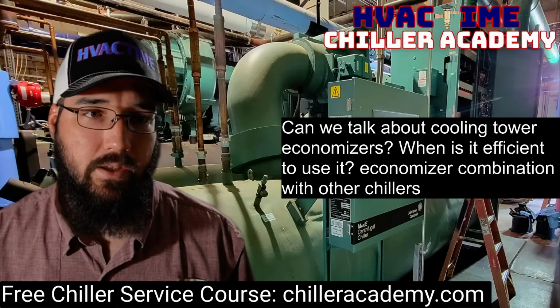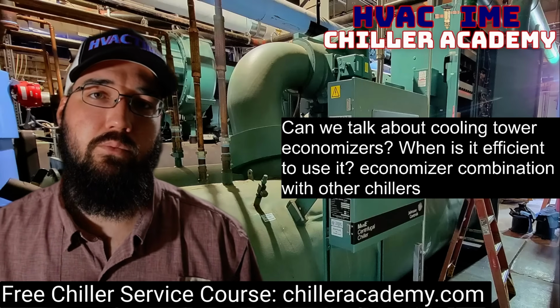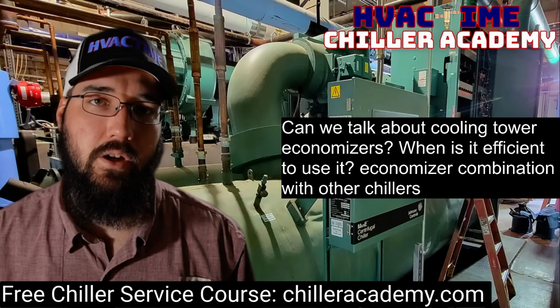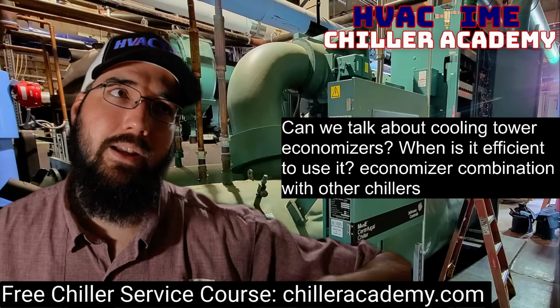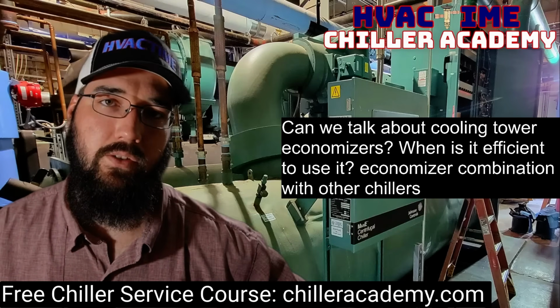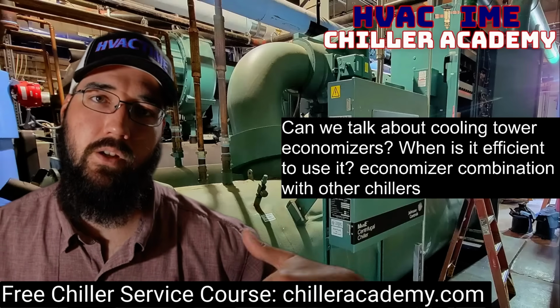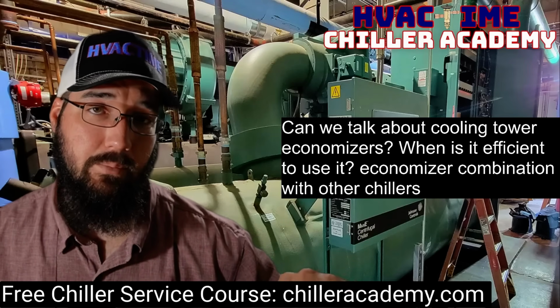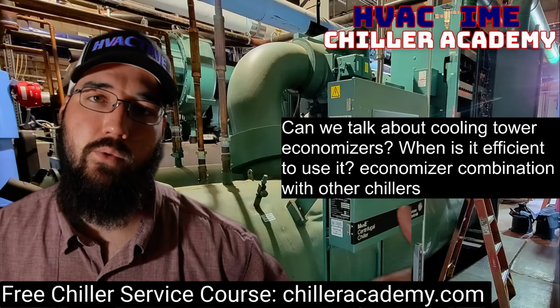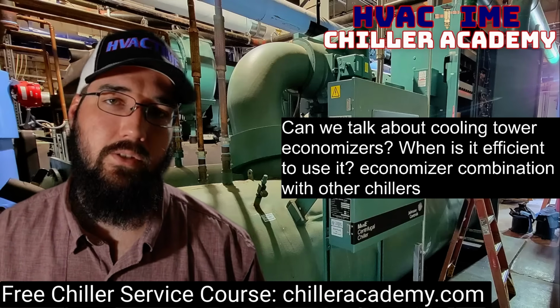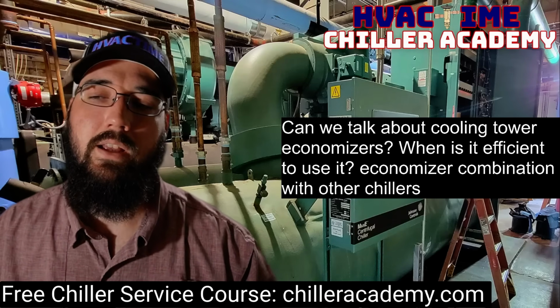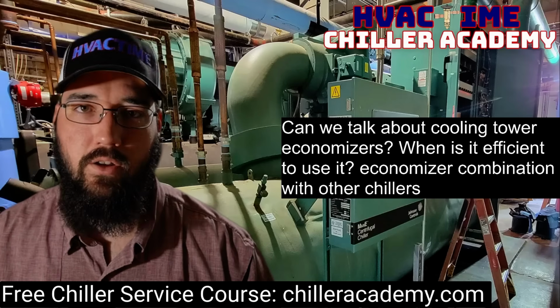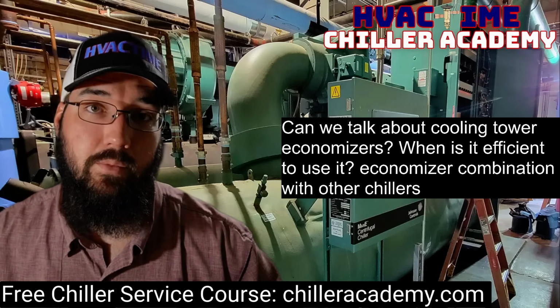Now, in some cases, when the plant will transition into economizer mode, the plants I've worked in will also raise the chill water set point a bit. So instead of running a 44, 45 degree set point, they may increase to a 48 or 50 degree. And it just depends on the building and what its humidity load is like, which in these cases, typically our humidity is down, right?